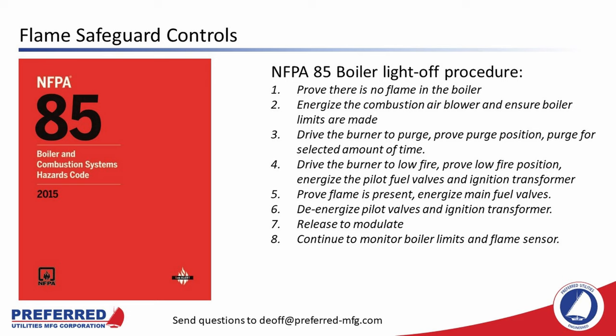After the furnace is completely purged, the flame safeguard will drive the burner to low fire, prove low fire position, energize the pilot fuel valves and ignition transformer, and then prove that the igniter flame is present before energizing the main fuel valves. Then the flame safeguard controller will de-energize the pilot valves and ignition transformer and release to modulate — which turns control of the fuel-air ratio over to a different controller. Once released, the flame safeguard continues to monitor the boiler limits and flame sensor.